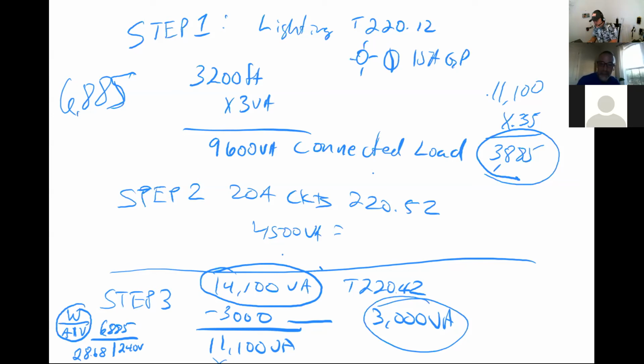You can find that in two different places in your code book. The easiest place is 230.79 on page 90, on the left-hand side. I'm just throwing this together because mentally that's where it comes into play — it may be on a different page, but it's related. So my service calculation, minimum code requirements, came out to be 28 amps, but 230.79C tells me the single-family dwelling can't be less than 100 amps.